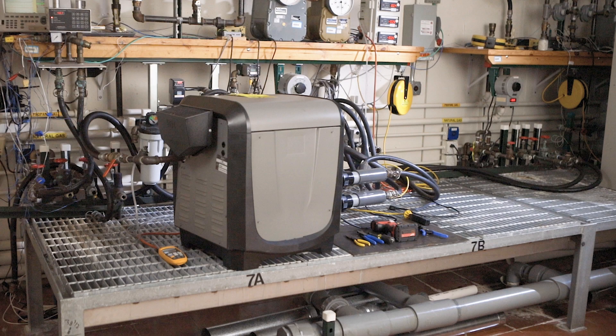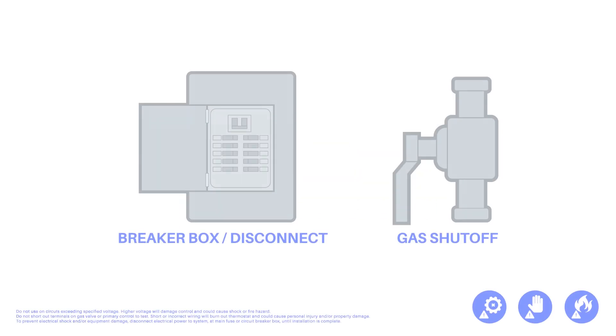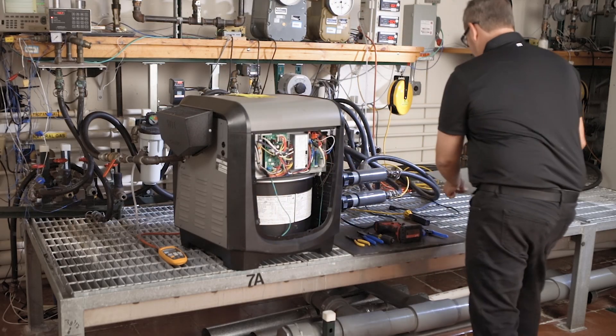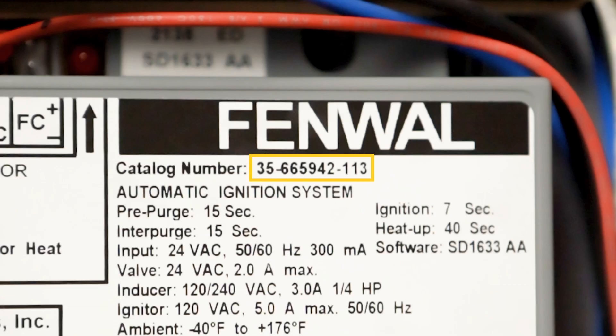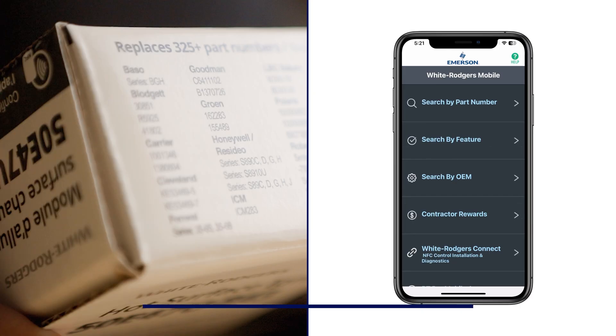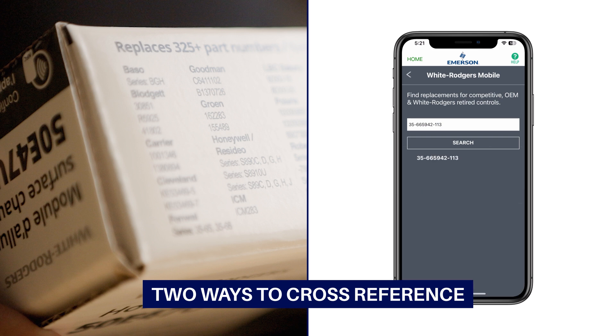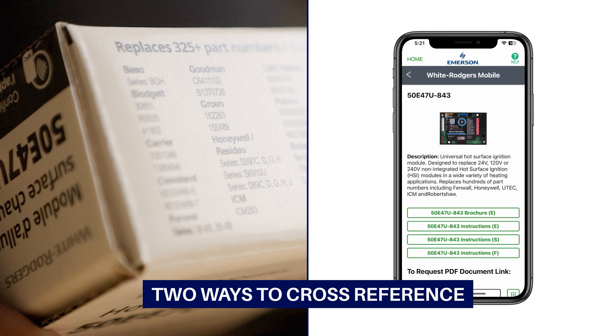For today's installation, a natural gas pool heater will be used. First, ensure power and gas are disconnected prior to servicing the unit. Remove the access panel. Check the part number on the existing control and verify it is one of the 325-plus modules that can be replaced with the 50E47U843. The carton contains the most popular cross-references, but for a complete list, use the White-Rodgers mobile app.